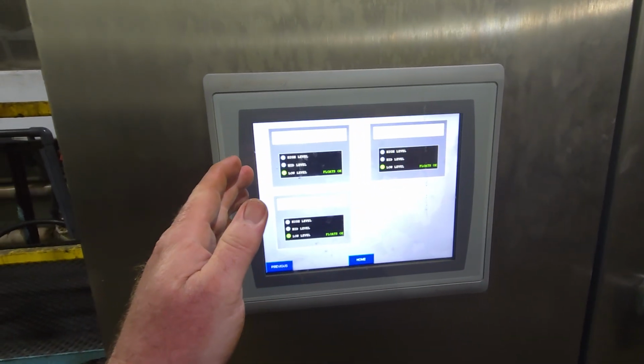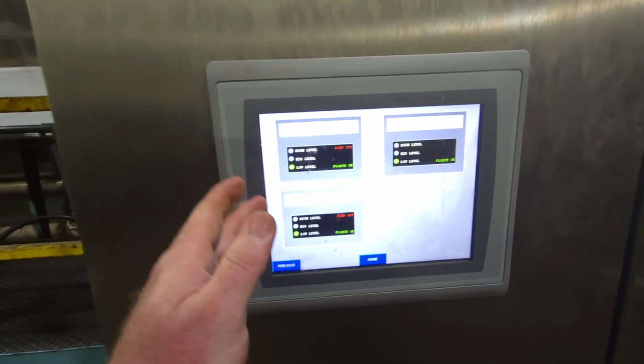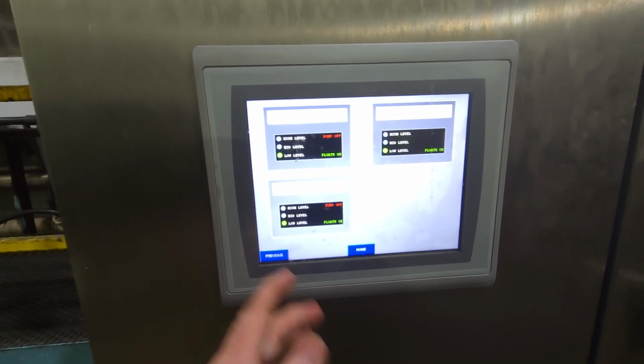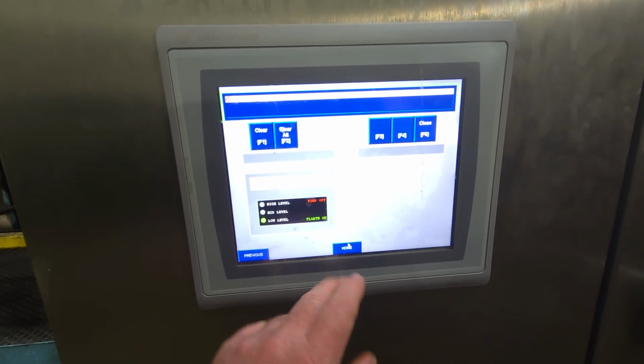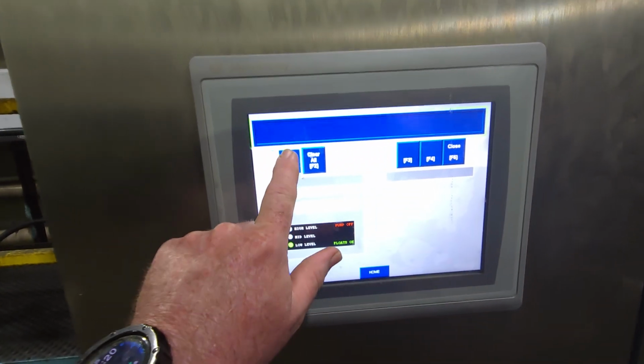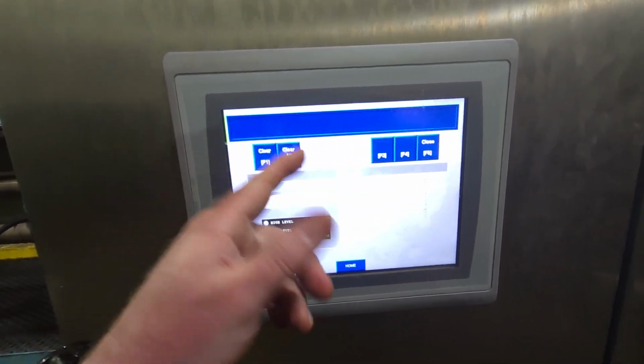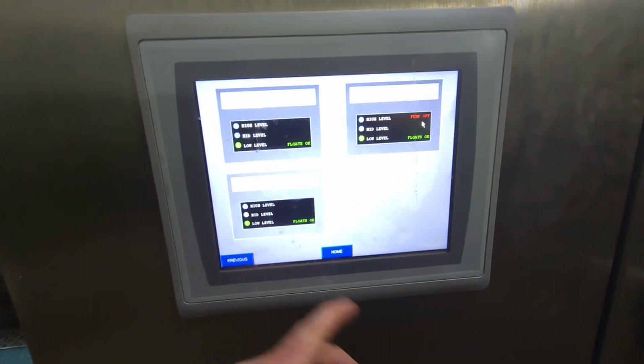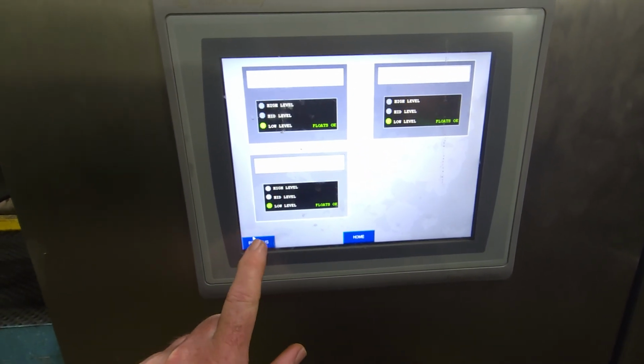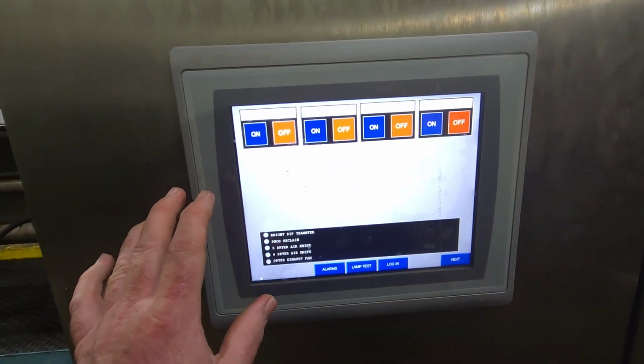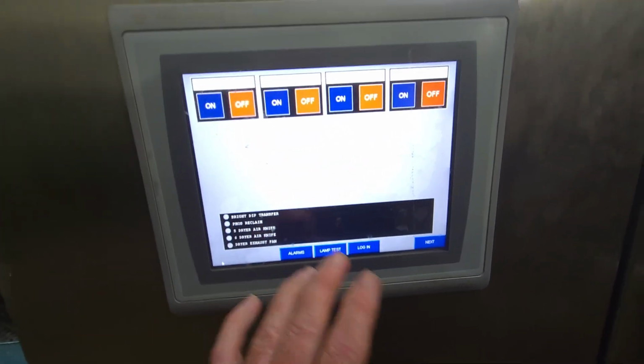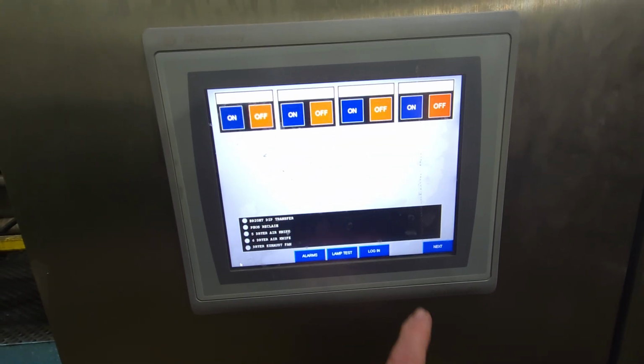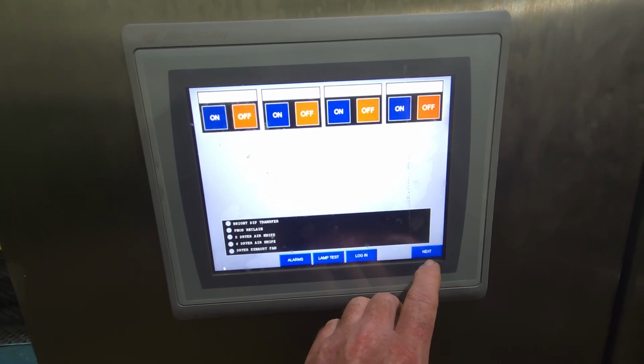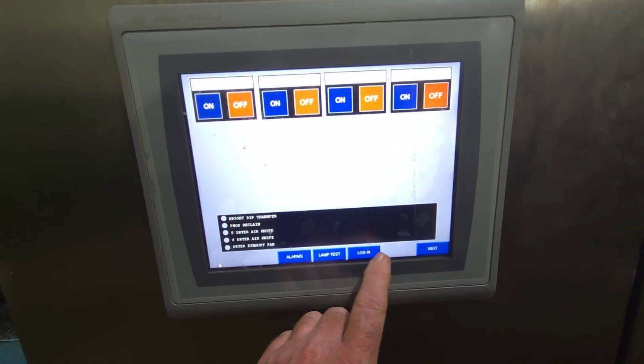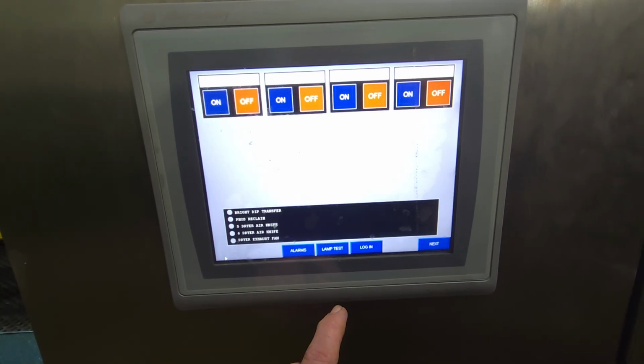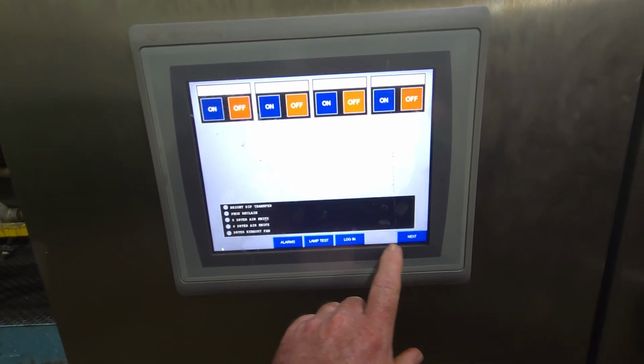But yeah, you can sit here and monitor it without going behind the line from right here to see how your flow's looking. If you do get an alarm, it'll be up across like this, clear alarm. I usually hit clear all and then close, just so you know. There is no way to shut it down or start it from here. So matter of fact, they might have it up on the panel. Never had to do it. Usually we never shut our sumps off. If we do, we shut it off at the switch in the back.